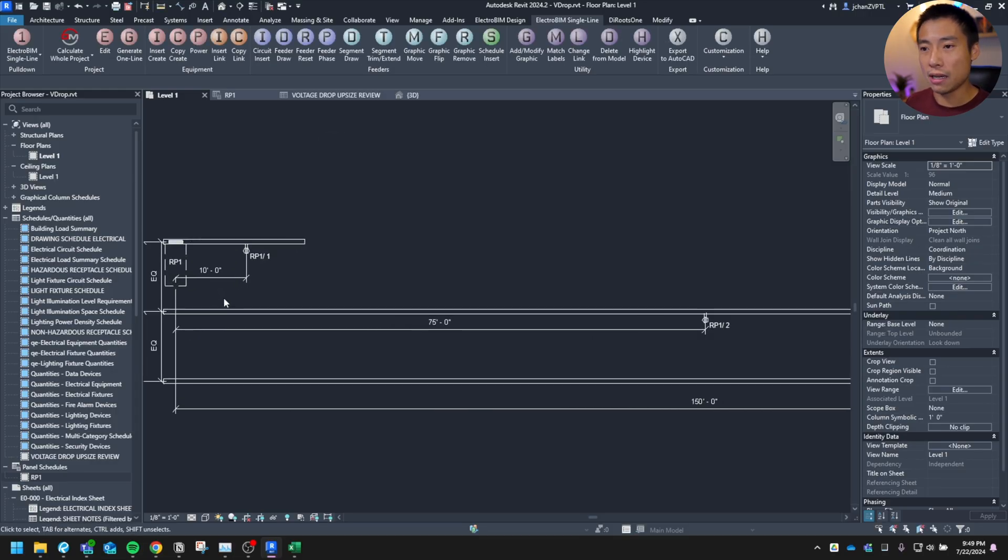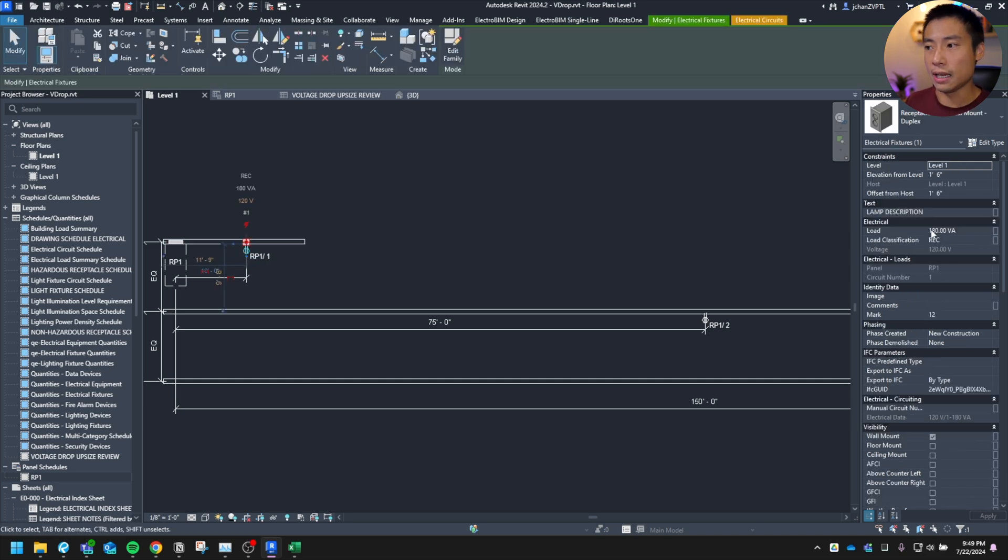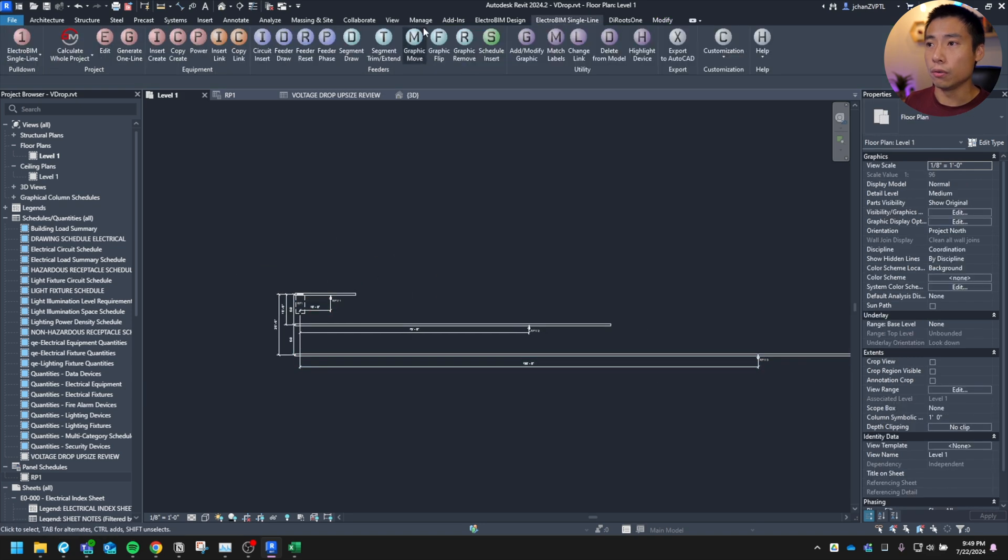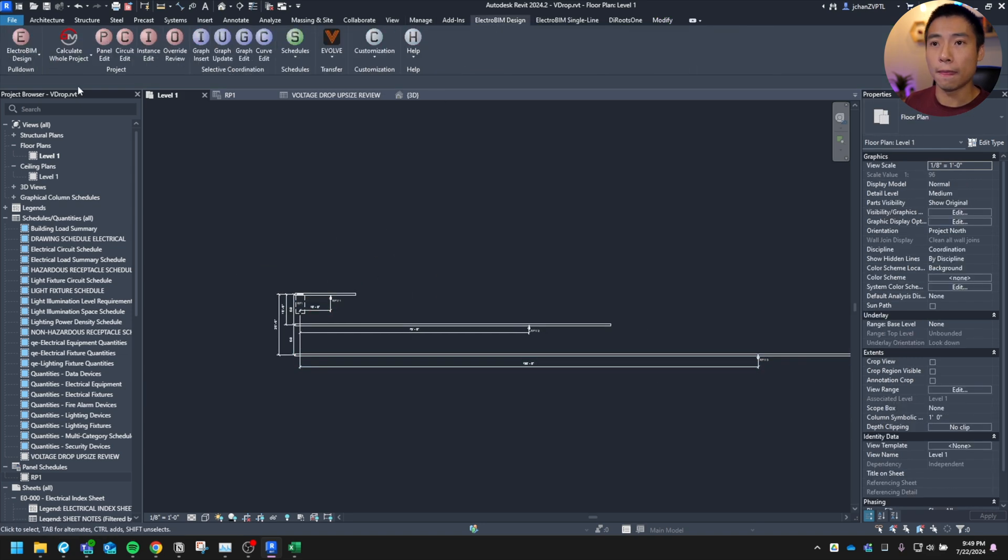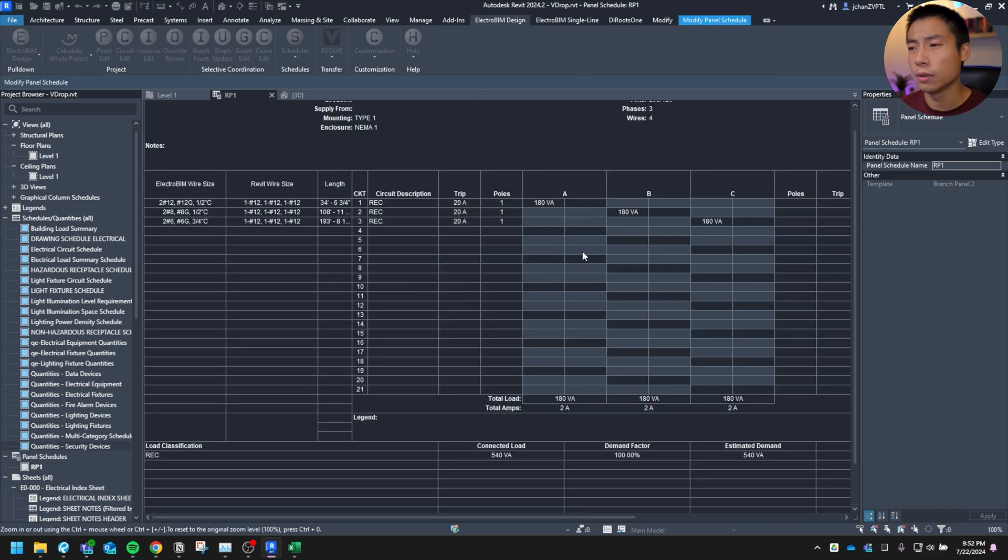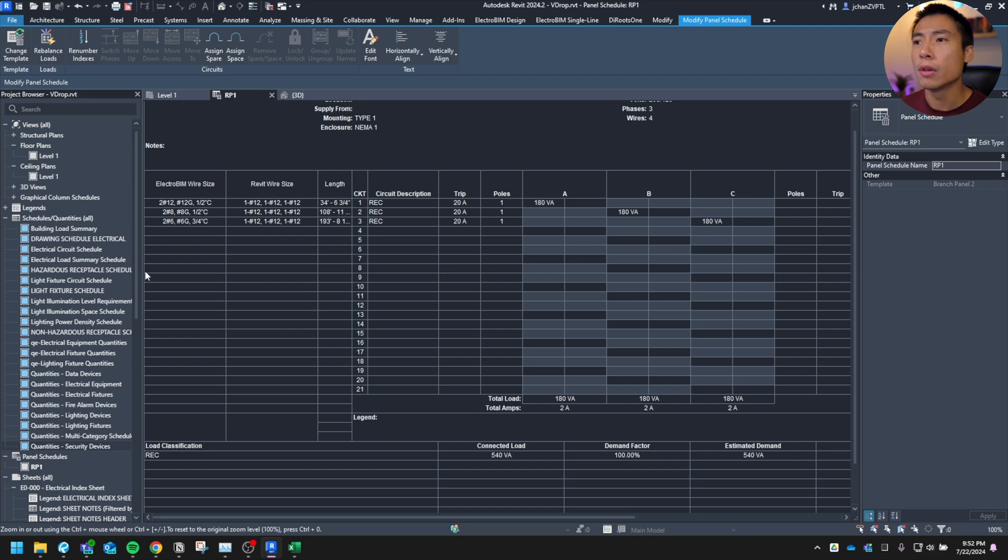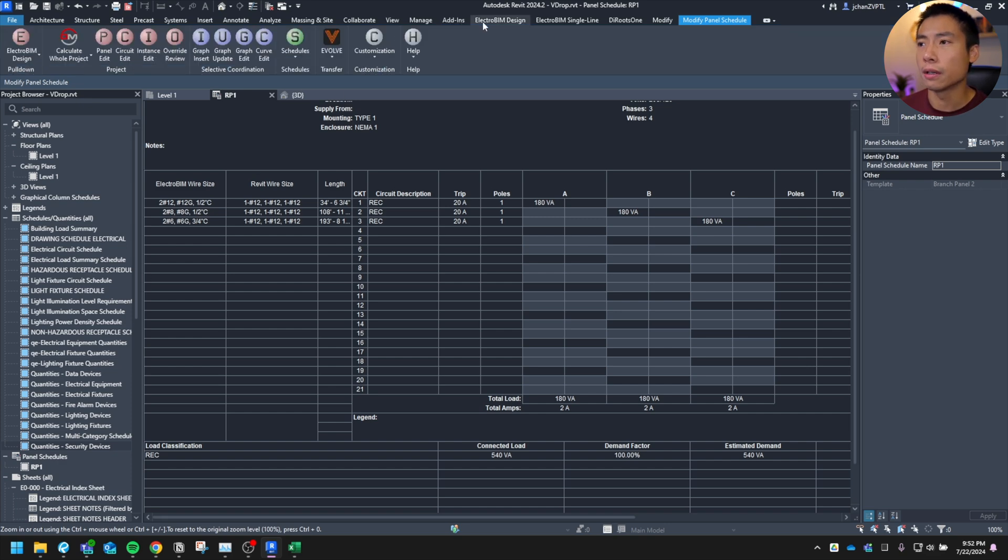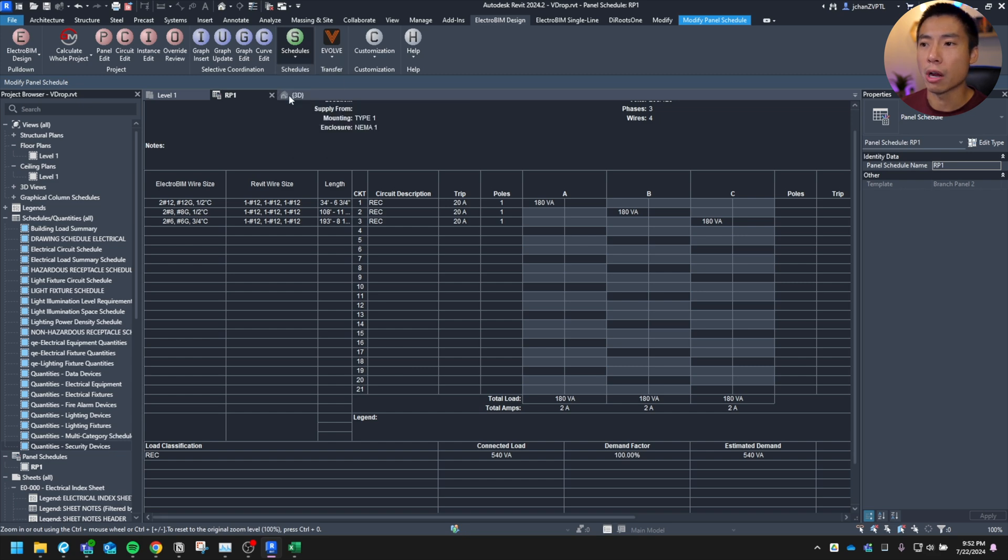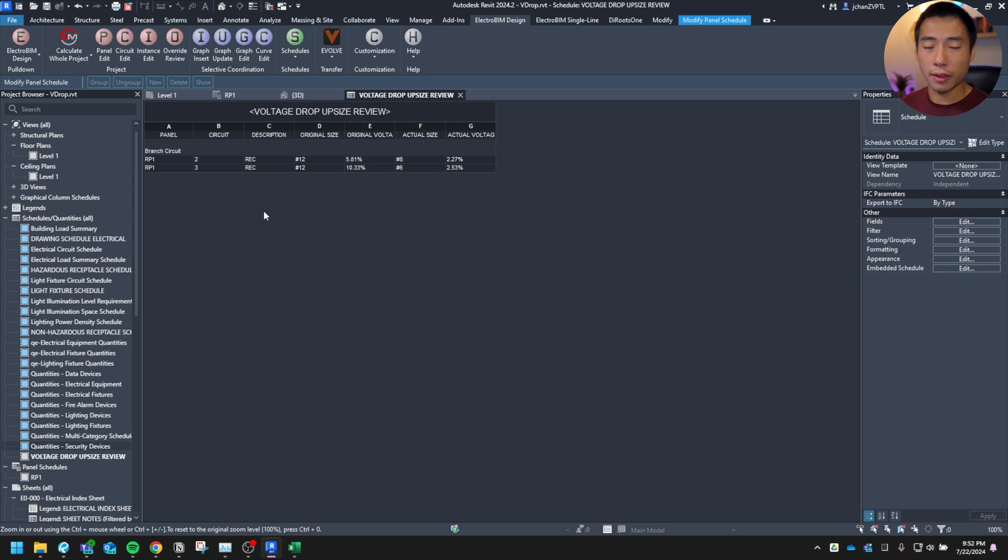So back here, I haven't changed anything. The receptacles are still where they are, but the loads are still at 180. Now, if I were to go over here to calculate the whole project, run the calculation. Okay. So then once the calculation runs, you'll have to go back up here to ElectroBIM design under schedule and open up voltage drop review. So this is the schedule that shows you everything that has been upsized.